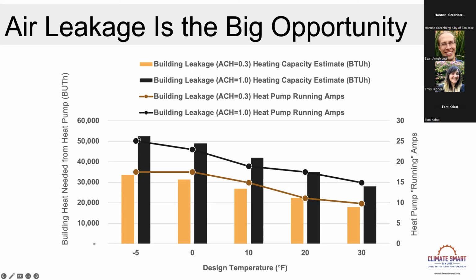So going from the leakage you have right now, shown in black here, where you might have a peak load of say 50,000 BTUs in the wintertime at California temperatures like 20 or 30 degrees: in black is your leaky house, in orange is the lowering of the heat load. On the right-hand side, you can see how when you lower the heat load, you also lower the running amps, the amount of power demanded. So less air leakage means less heat pump has to run. There's significant savings there from going around with the caulk gun, reducing the amount of heat pump you have to put in, the power demand, by like a third. That's a big savings in power demand, which is the point of this talk.